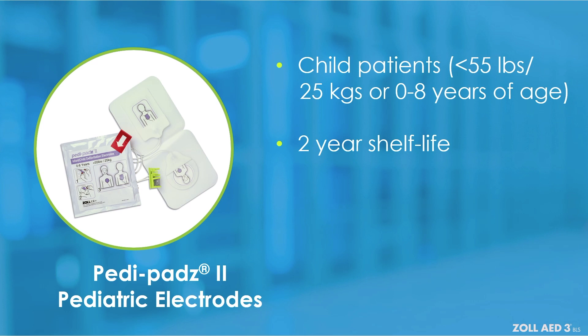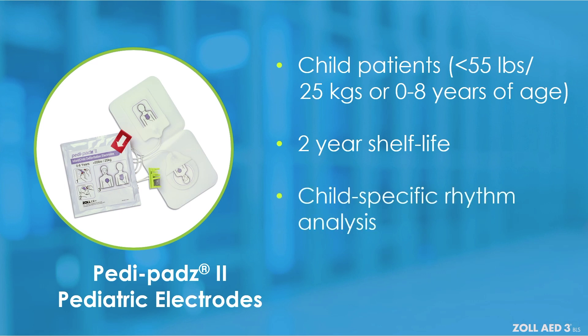When inserted into the Zoll AED-3BLS, the Pedi-padz II pediatric electrodes will initiate a child-specific rhythm analysis, illuminate the child mode indicator on the device, and display an ECG rhythm on the dashboard.